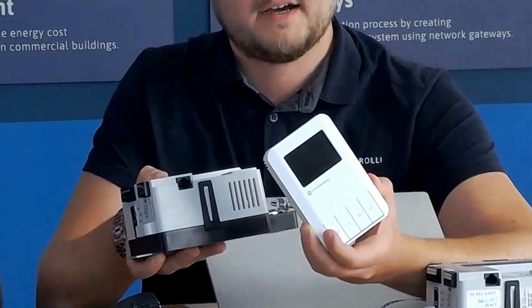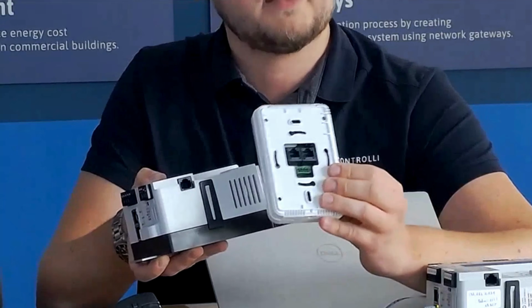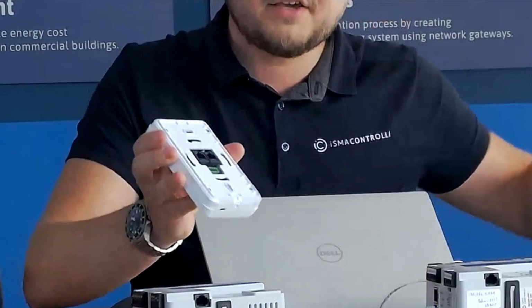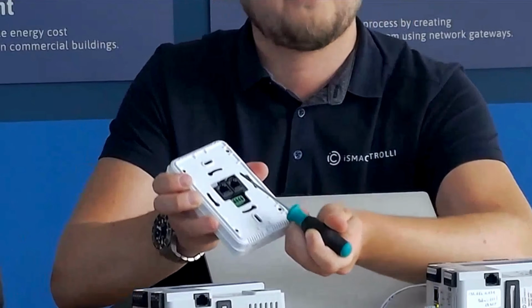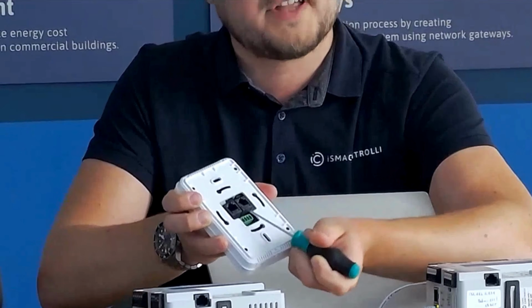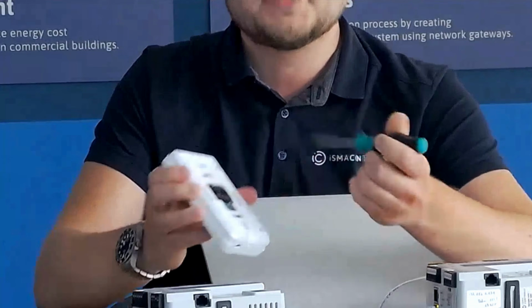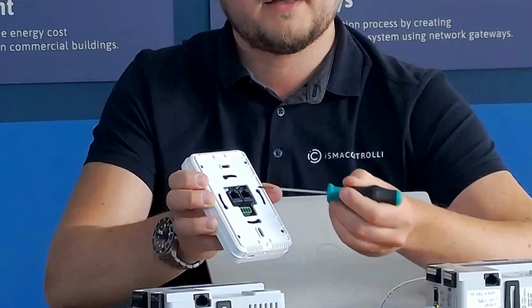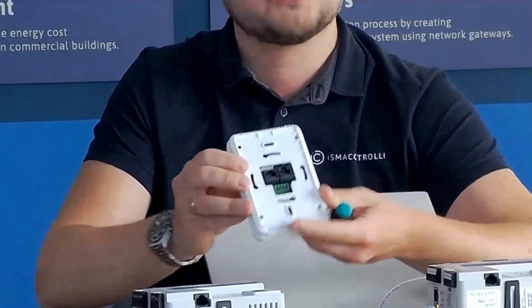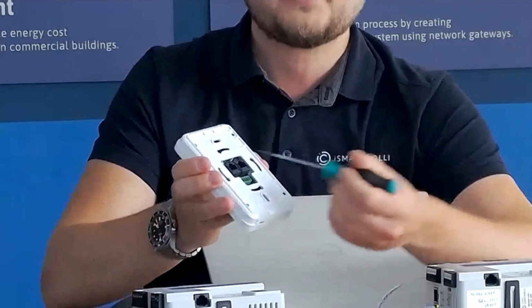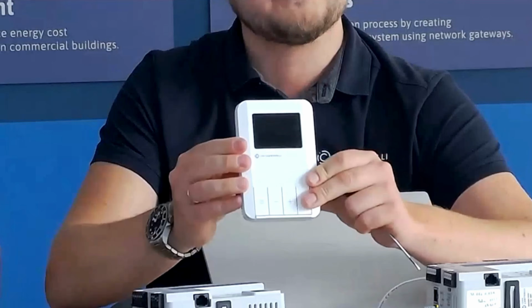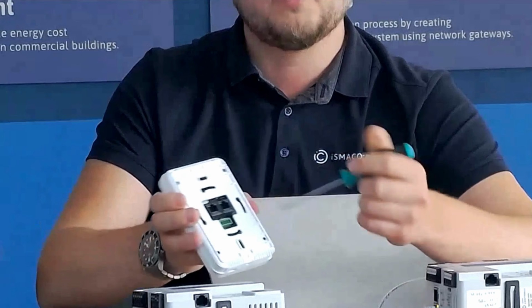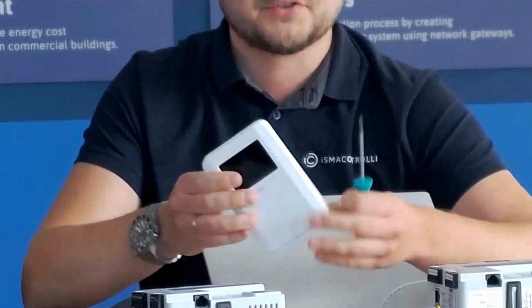Our panels are BACnet MSTP and Modbus RTU, and on the back here, let me put the controller down there. On the back you can see two RJ45 ports, which are used for the MSTP connection and for powering the CP unit directly from the controller. So there is no need to power up the CP unit additionally. It's powered from the controller itself. And the other cool feature is you can daisy chain up to 5 CP units on the network, and they will all be powered directly from the VAV controller and communicate with it. So you can have 2-3 space sensors and average them on a large room.